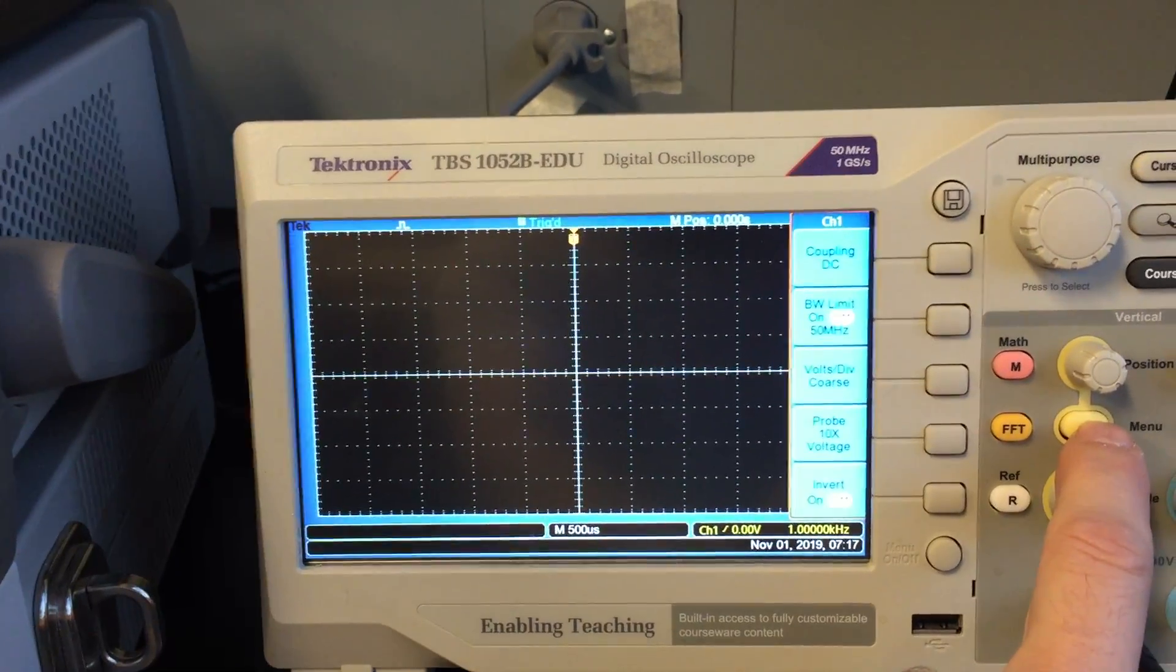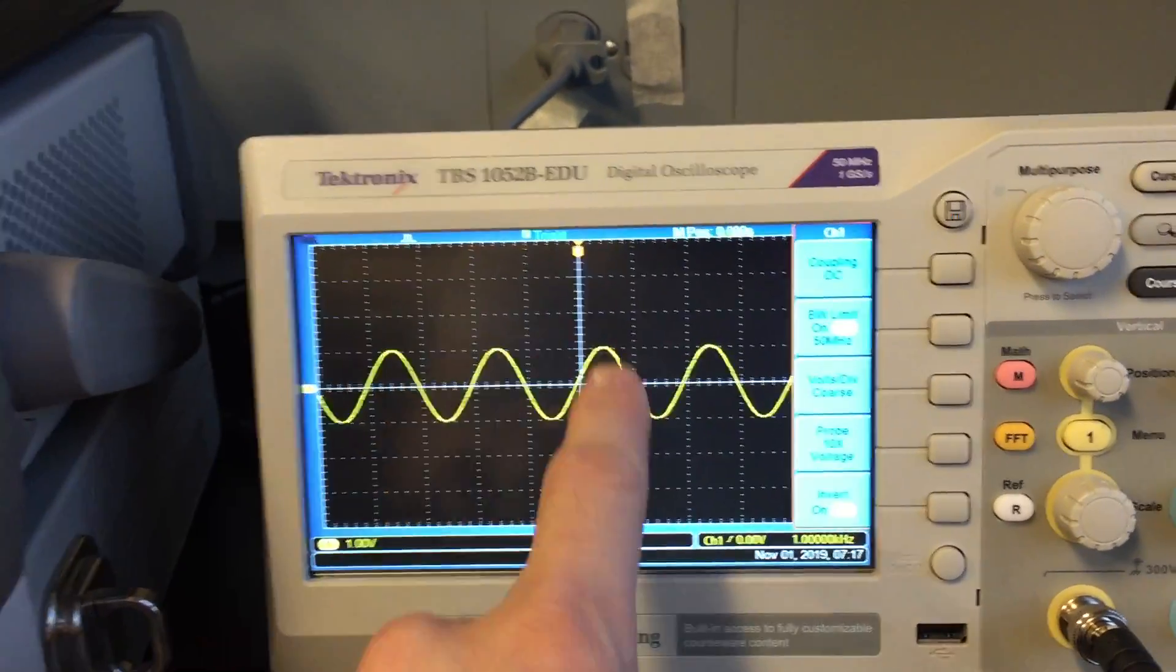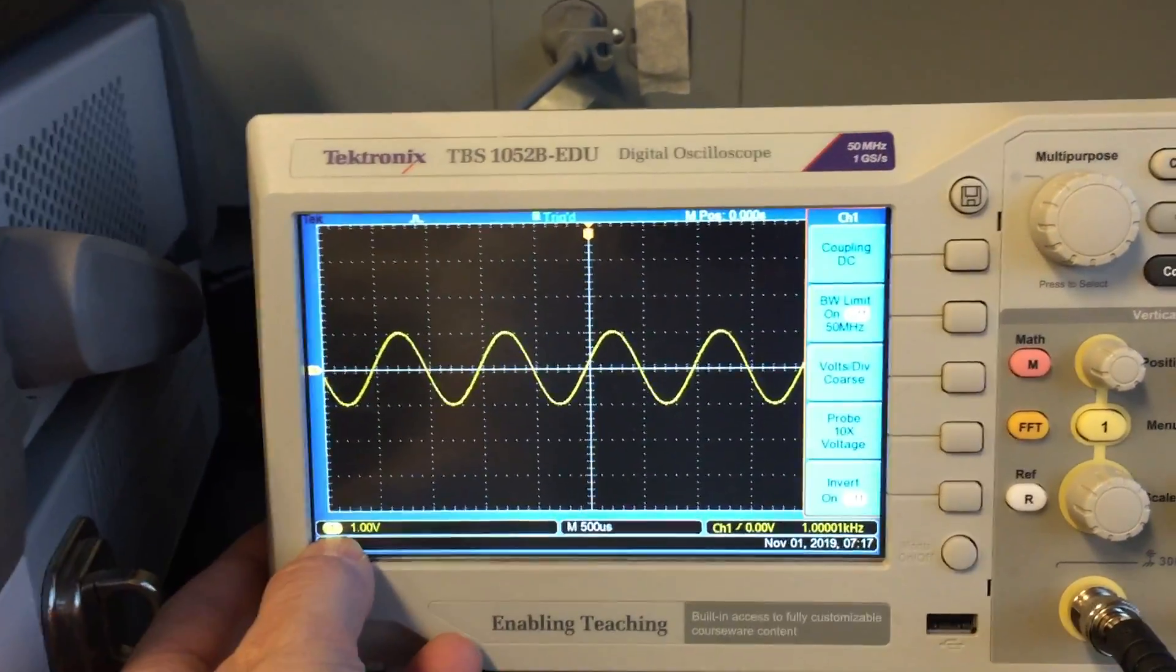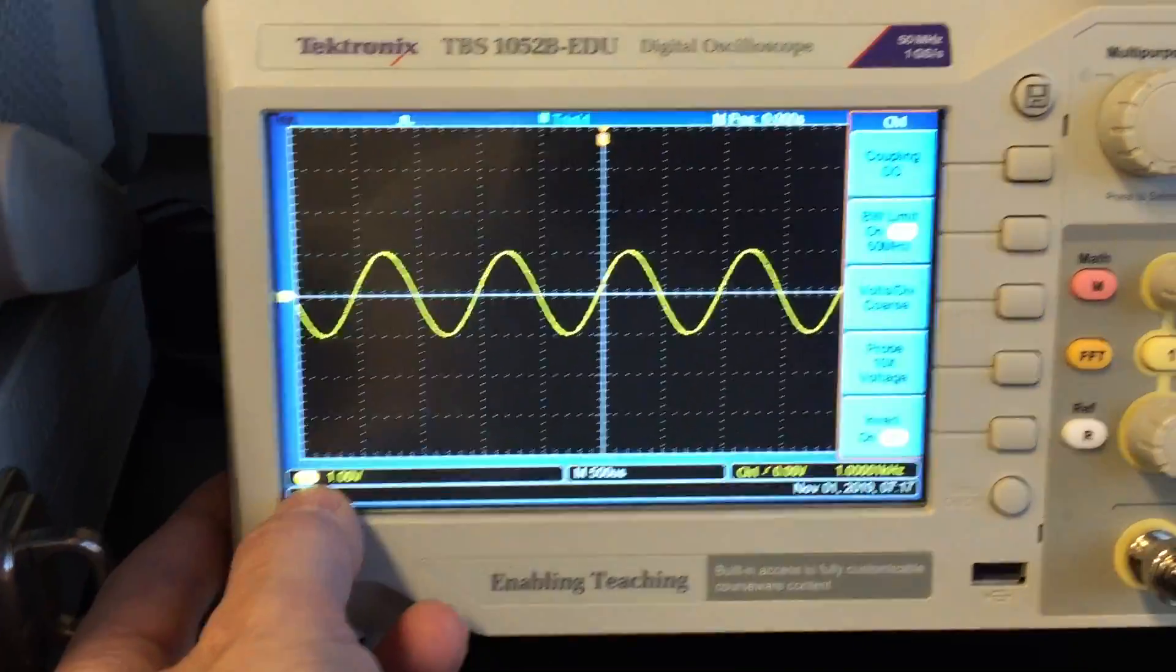So if the trace is gone, there's no indication down here, no volts per division. Push the number one button. Trace will either appear or not appear. But more importantly, it says right here the number one is on. Number one channel is on. It's on one volt per division.